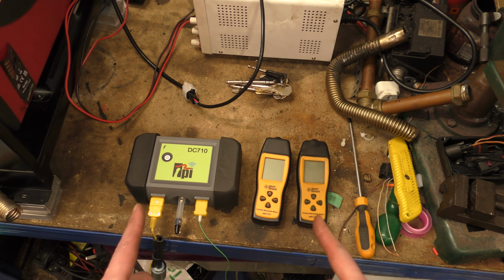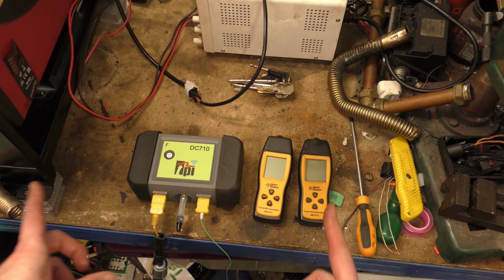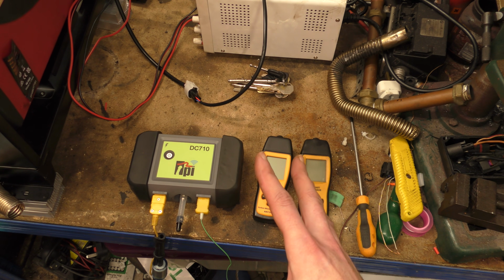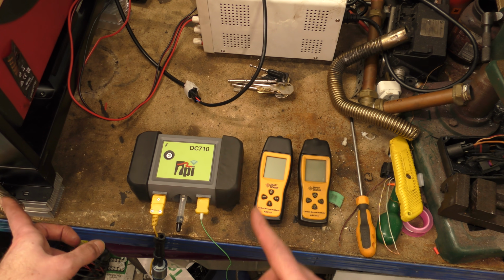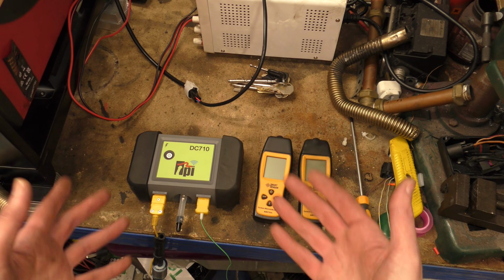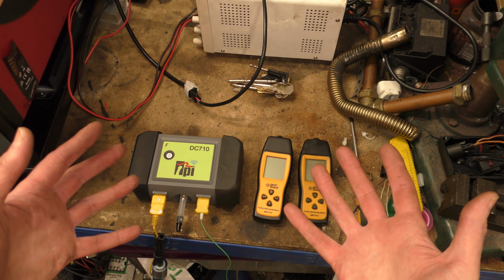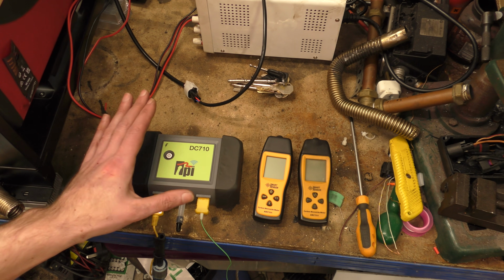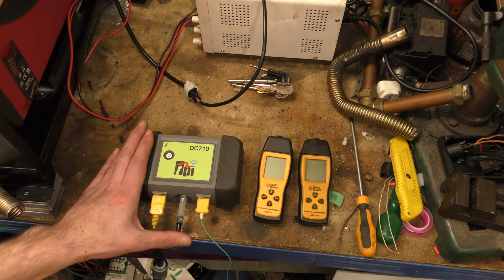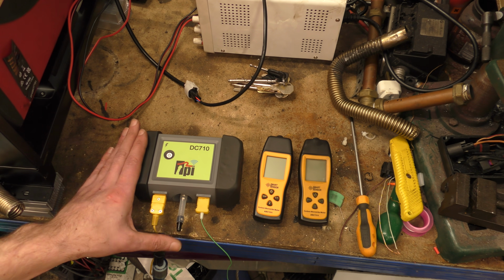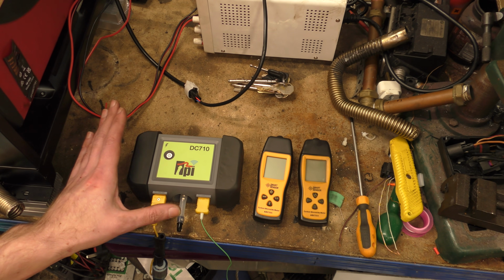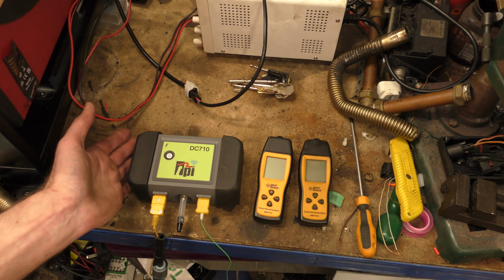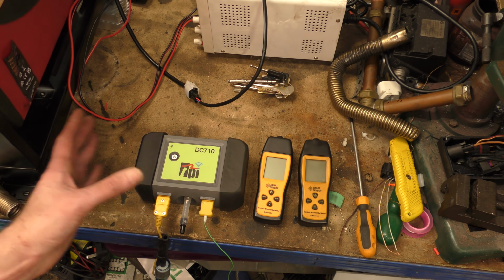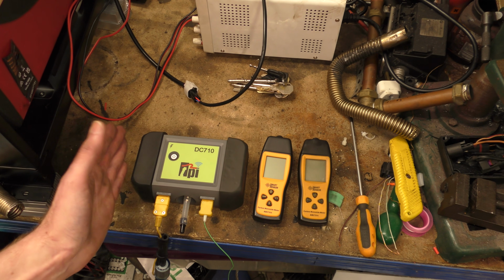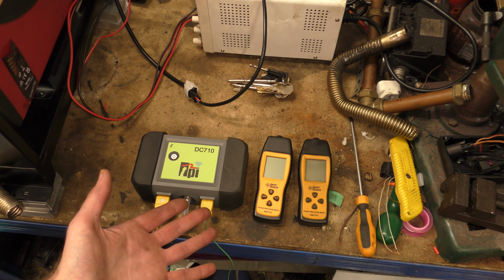What we should do at some point is take a comparative carbon monoxide reading - leave it running, tuned, and see what the carbon monoxide inside the exhaust is compared to what the cheap one tells you, so we'll have an offset to work with. Obviously this combustion analyzer is very expensive, and don't expect your everyday person to rush out and buy one just to tune their diesel heater. But it's interesting - if you're an installer who fits a lot of diesel heaters and want them as well tuned as possible before they leave you, something like this might be advantageous to have in your arsenal of tools.